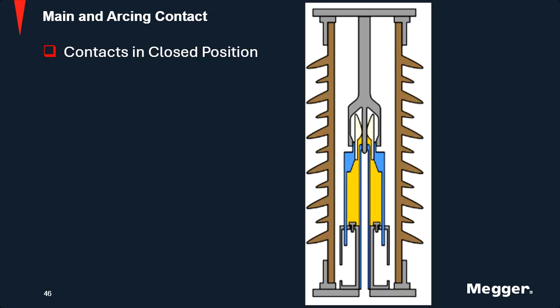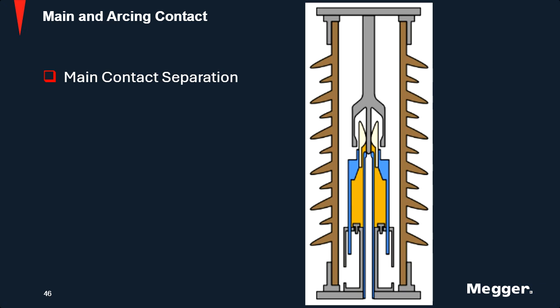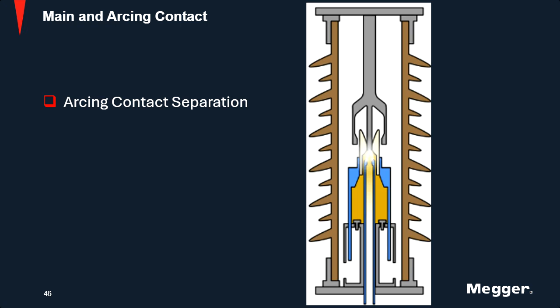So here's a representation of how the interrupter works and what you would see inside your interrupter while you're doing an opening command. Your contacts are in a closed state. If you look right here, the blue and the gray are your main contacts. The top portion of it is stationary. The bottom portion is your moving contacts. So your blue and gray right there are your main contacts, and this rod right here is your secondary contact, your arcing contact. So you give the open command, the main contact separates. All the current that was going through the main contact is now going through the arcing contact. All this is meant to save your actual main contacts. And as it separates, the arcing starts from the arcing contact.